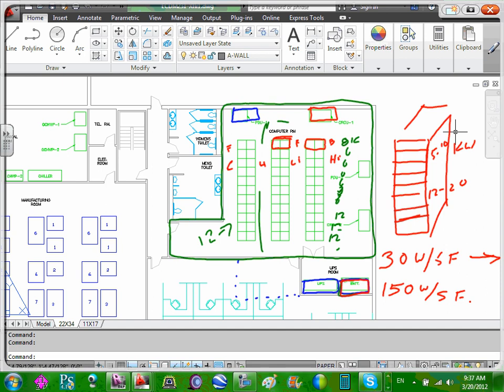I think I'll be okay. But what I've asked for and what I'm going to change is for each server rack, I need 2 whips to my PDUs. And so each of those whips, if I have to change this, I will, but I think I'll be okay. I'm saying the whips would be 30 amp, 3-phase, and don't need neutrals in my equipment, 3-wire, 208. So I need a whip from my red PDU and a whip from my blue PDU to each rack with 30 amp, 3-phase, 3-wire, 208.